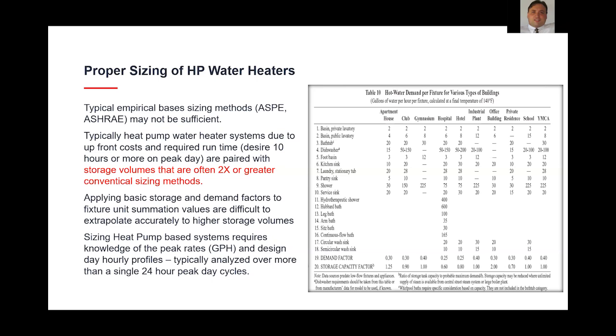In that analogy, you've got an ice storage chiller, you're load leveling it. Your goal is to never run out of ice. Some hours you're burning ice, some hours you're storing ice, but you're keeping that chiller loaded through the majority of the hours. And that's the goal with these systems. We like to see these heat pump water heating systems designed on a peak design day to have at least 10 hours of runtime, because under average conditions, they'll see less than that, and we don't want to get into excess cycling. And there can be lockouts if those number of cycles are exceeded.